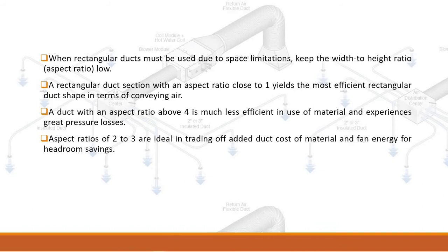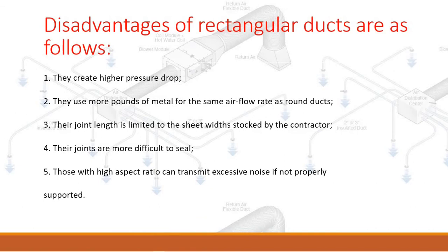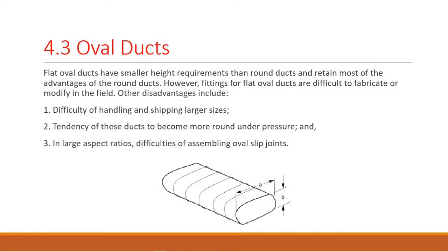Aspect ratios of 2 to 3 are ideal in trading off added duct cost and fan energy for headroom savings. Disadvantages of rectangular ducts include: one, higher pressure drop; two, more pounds of metal for the same airflow rate as round ducts; three, joint length limited to sheet width; four, joints more difficult to seal; five, high aspect ratio ducts can transmit excessive noise if not properly supported.